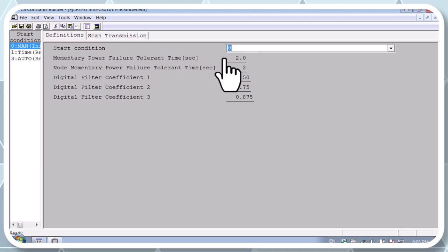And my friends, my suggestion is to use strong filtering or medium filtering when you have a signal with higher noise. So an example is the tank level or the pressure inside the water tank. And sometimes you must avoid filtering, for example, in turbine speed or emergency shutdown signals, you must avoid the filtering.